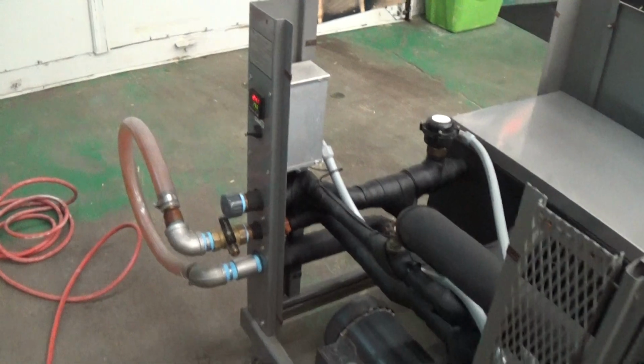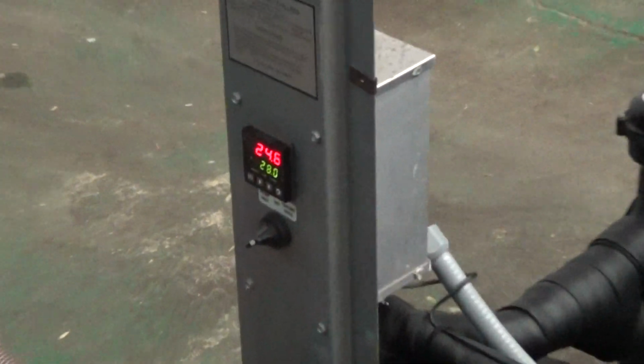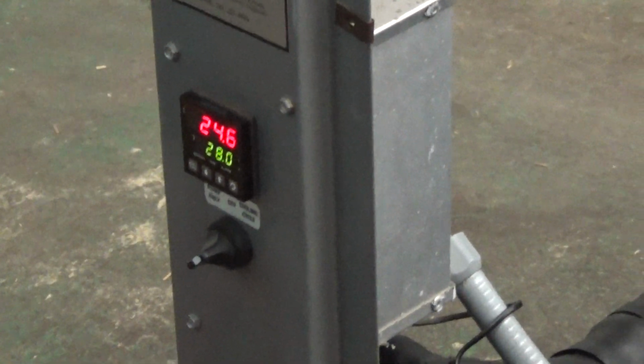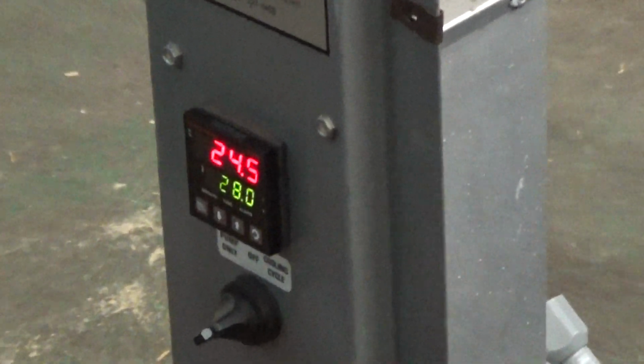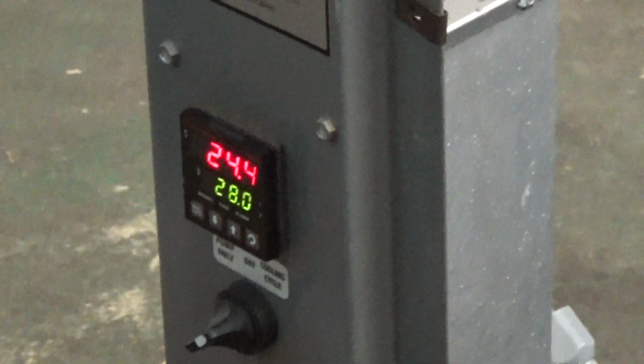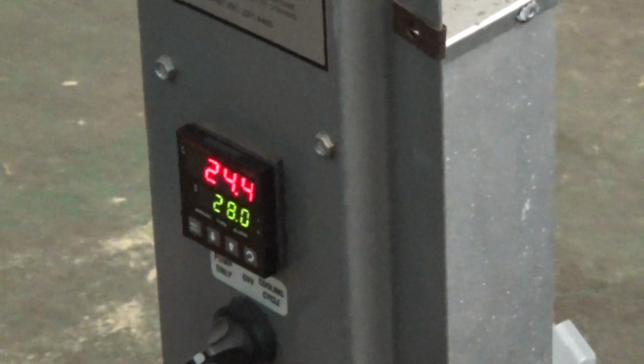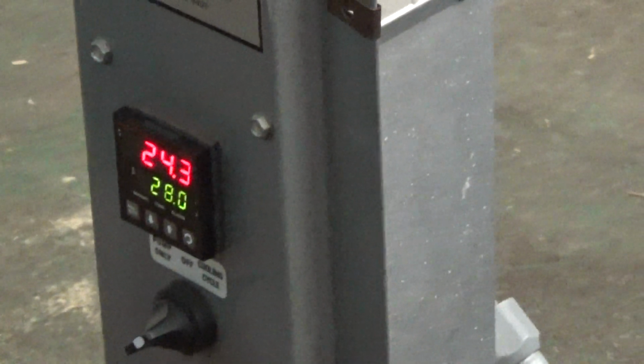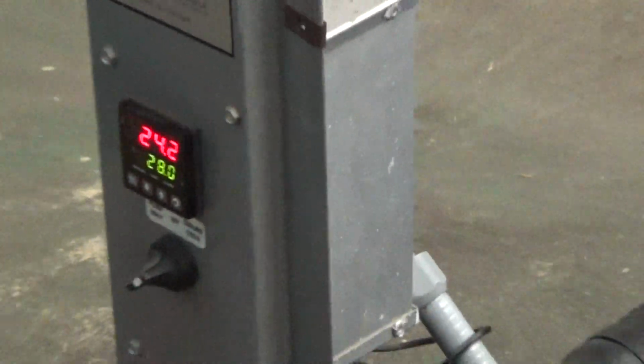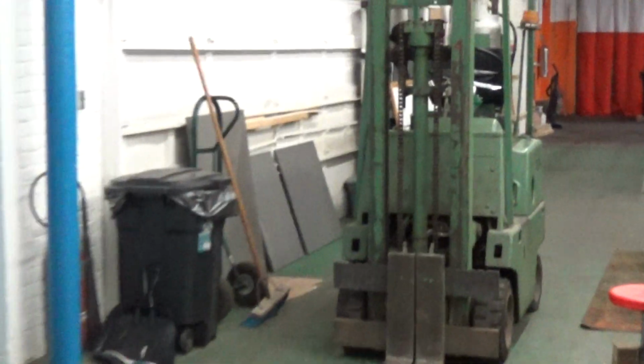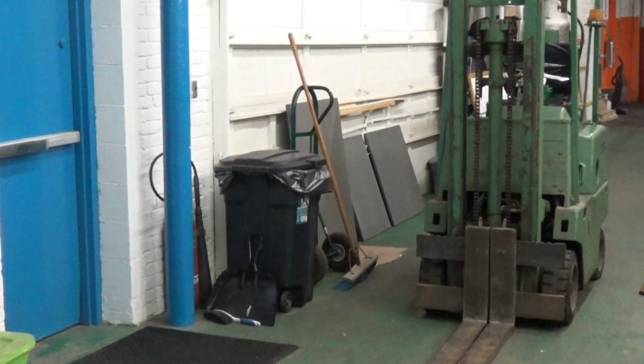That's very important. So again, while I was talking, we got to 3 degrees below set point, which is 25. And as you can see, there's still a little bit of residual cooling in there. And the compressor did shut off while I was talking about that crankcase heater. So again, we have all the covers. In fact, the top cover, we had a little ding in it, and a scratch. We stripped it down or sanded it down.